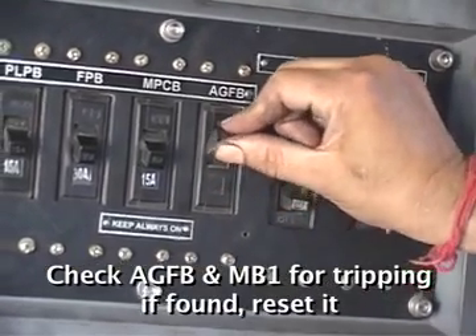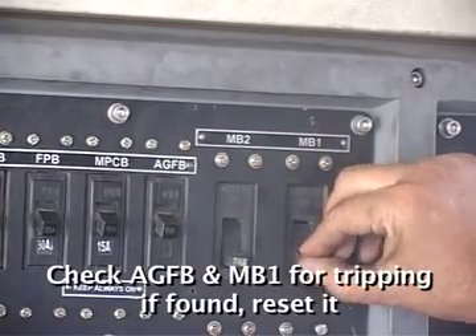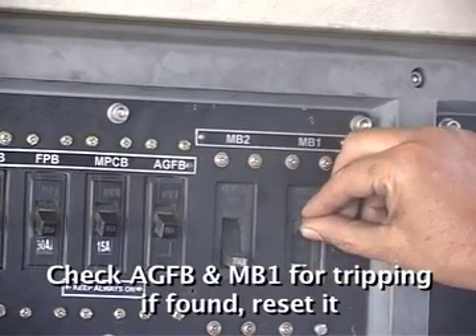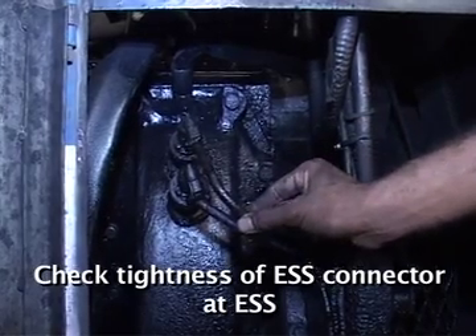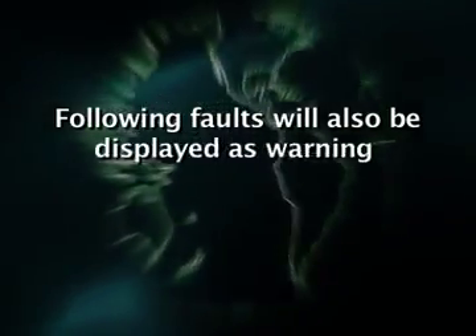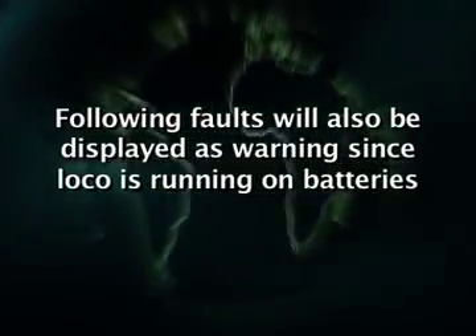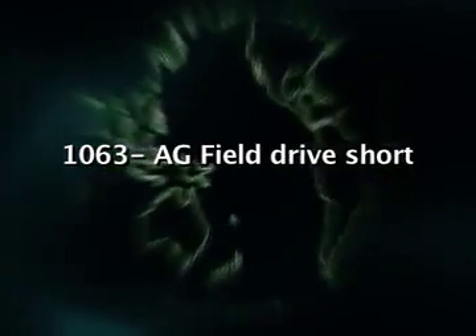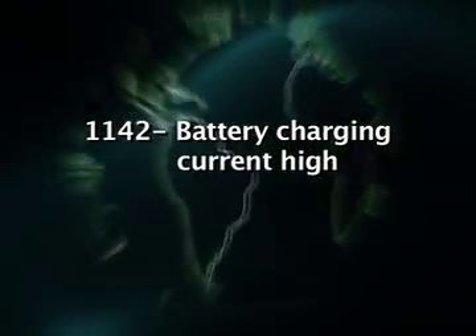Action by driver. Check for tripped AGFB and MB1 breakers. If any one is found tripped, reset it. Check for tightness of ESS connector at ESS. Following faults will also be displayed as warning since loco is running on batteries. 1062 battery voltage is high. 1063 AG field drive short. 1141 AG output high fault. 1142 battery charging current high.